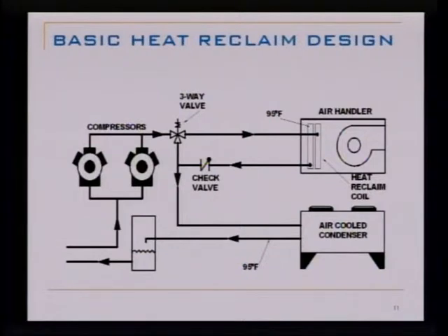After the compressors, before the hot refrigerant goes up to the roof to be thrown away in the condenser, through a three-way valve, whenever there's heat demand in the store, you send that hot refrigerant gas through the air handler and condense it in the main air handler that's supplying heat to the store.